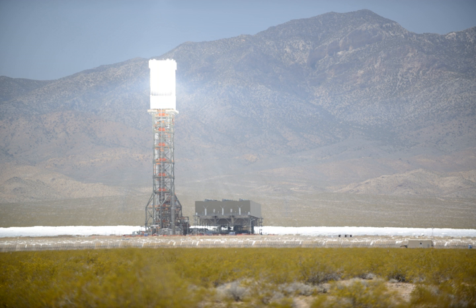Some concentrating solar power towers are air-cooled instead of water-cooled, to avoid using limited desert water. Flat glass is used instead of the more expensive curved glass. Thermal storage in molten salt containers continues producing electricity while the sun is not shining. Steam is heated to 500 degrees Celsius to drive turbines coupled to generators which produce electricity. Control systems supervise and control all plant activity including the heliostat array positions, alarms, and other data acquisition and communication.